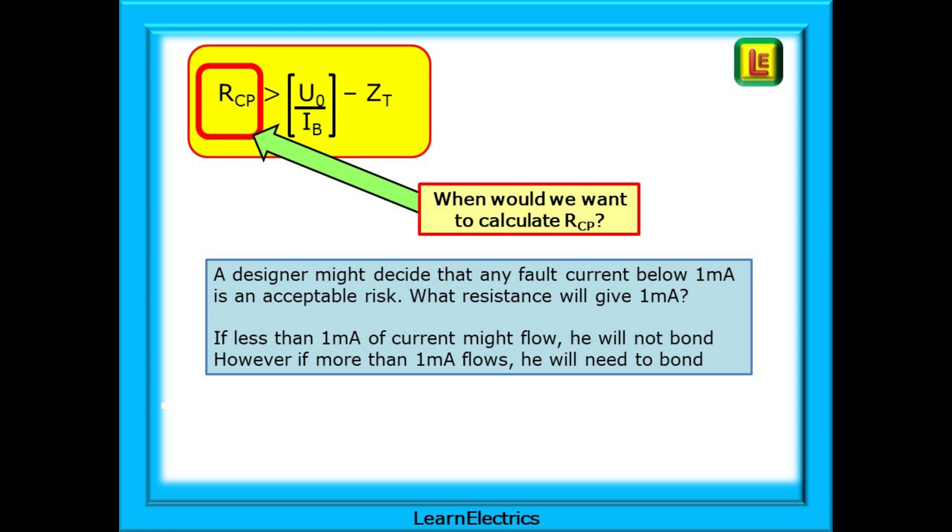A designer might decide that any fault current below 1 milliamp is an acceptable risk. If less than 1 milliamp of current might flow, he will not bond the conductive parts. However, if more than 1 milliamp flows, he or she has decided that they will need to bond, as these will now be extraneous conductive parts. If the designer knows the maximum current that they do not want to exceed, the formula will tell them the minimum resistance that must exist. Let's calculate this example.